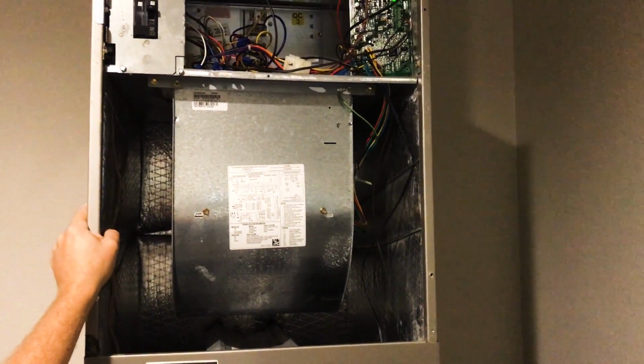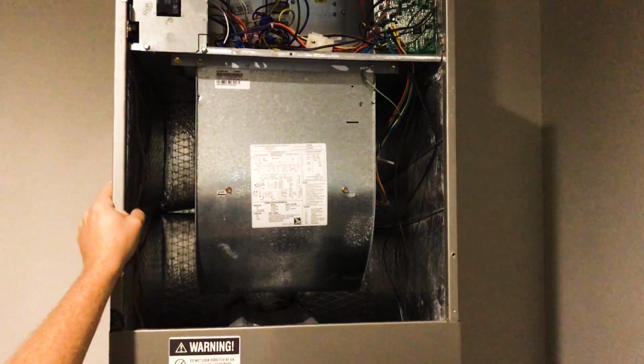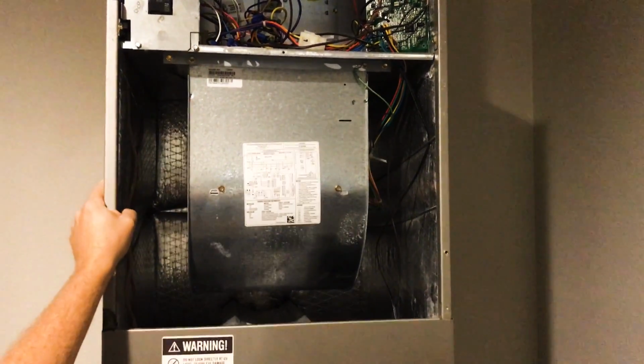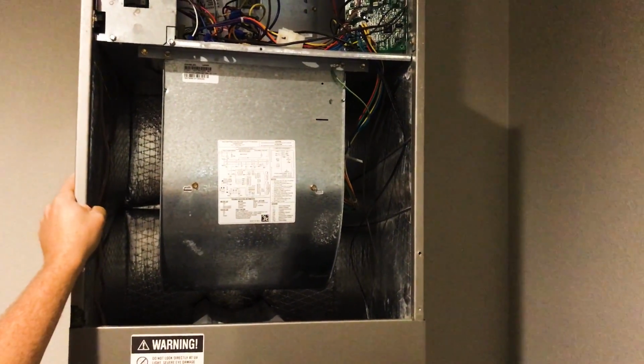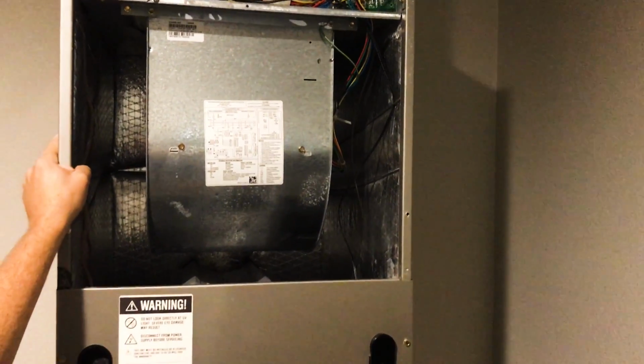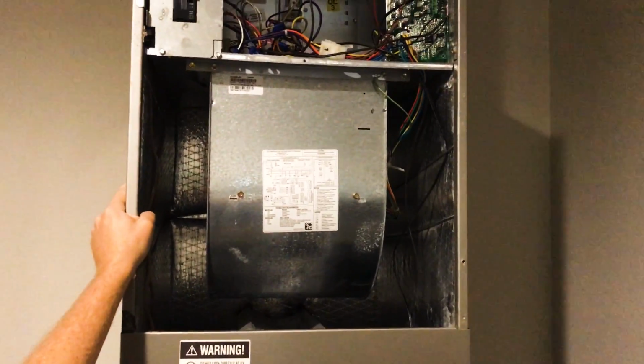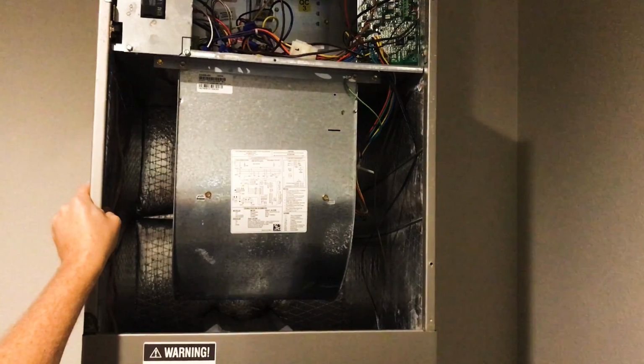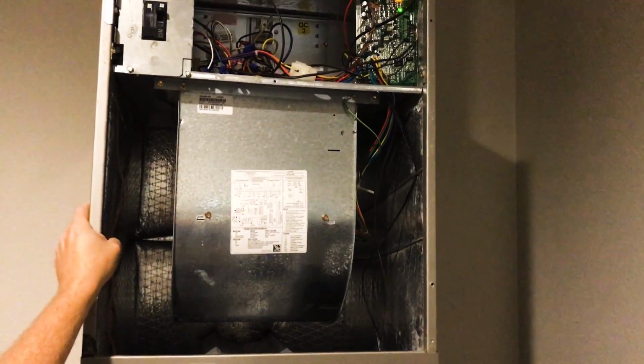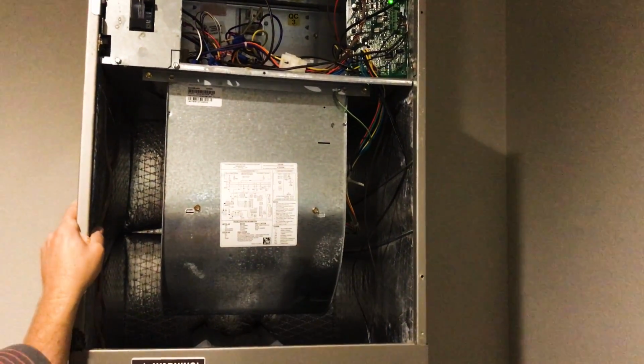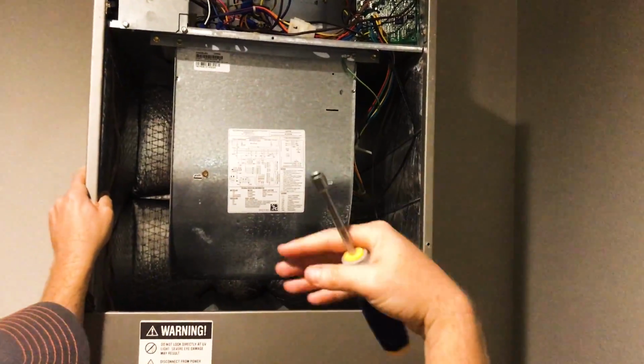Pull it off, disconnect it, and we're gonna ohm out the motor, just because that's a process that the manufacturer says they want you to follow, to check the motor against the module. But at this point, I'm as confident as I can be that it is the actual module. I've checked all the visual connections. In this particular case, we're communicating with the indoor board, so the thermostat's communicating with the board. It's just that the board isn't communicating with the blower.